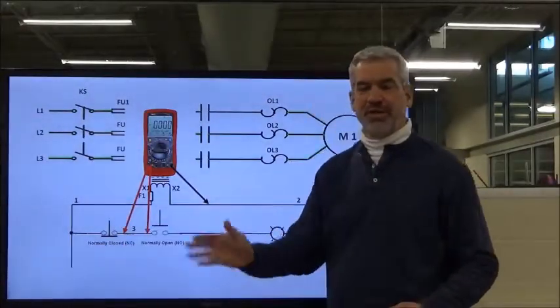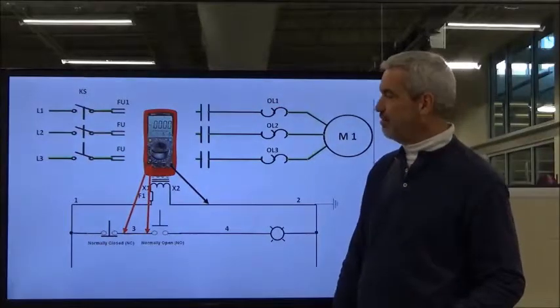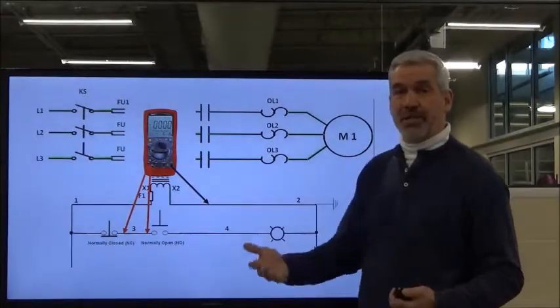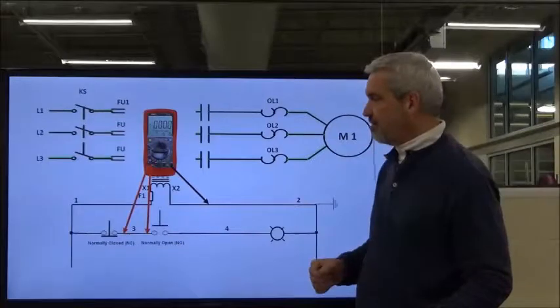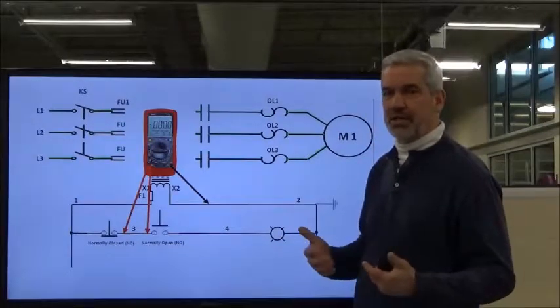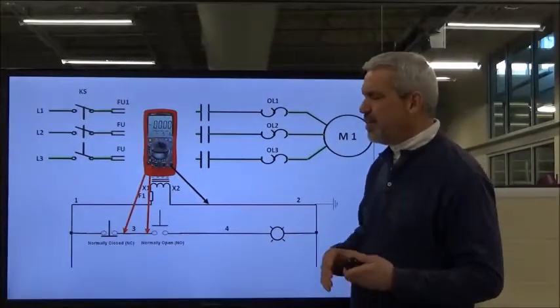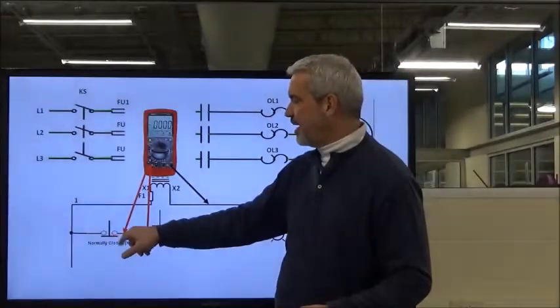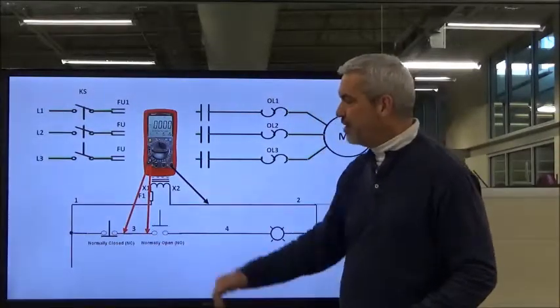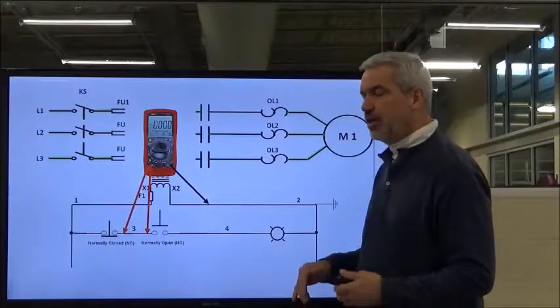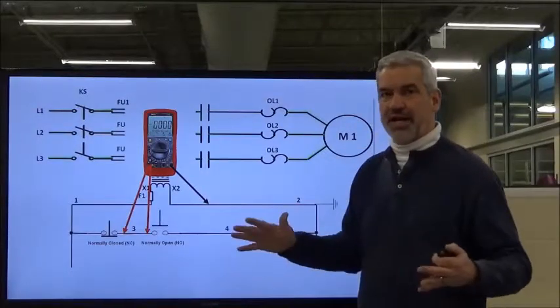Fork trucks run over wire all the time and crush it and break it, and all kinds of things happen. They burn in two as part of the process. Sometimes they're around hot molten aluminum or some type of furnace, so you never know what's going to happen. So you check it coming out of here, make sure you've got it here, and continue to step through that, looking for the place where the voltage just kind of disappears.